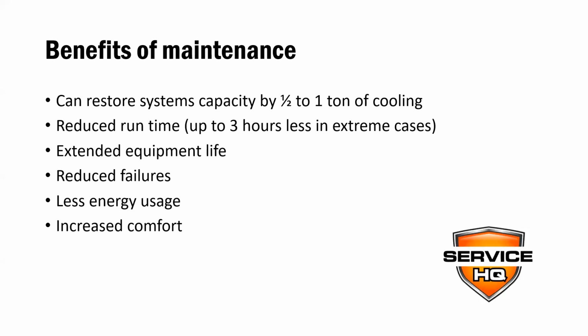It can also reduce runtime by up to 3 hours in any 24-hour period in some extreme cases. So that's an extreme case. What about if it's just lightly dirty? I mean, if you could reduce your air conditioning runtime by 1 hour, what's that going to do to your equipment? It's going to extend the equipment's life. You're probably going to have less failures because it's not running as much. It's not working as hard. You're definitely going to use less energy. Anytime the system's not running, you're not using electricity. And of course, increased comfort. The house is just going to be more comfortable.